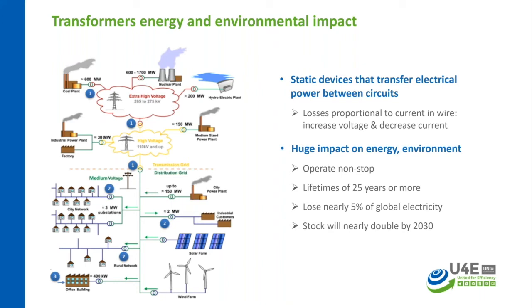In some cases, it will be even higher, and therefore this transformer becomes a very important product to regulate. Another important thing from the utility perspective is that this is a product where the technical losses are higher, and there is the potential to reduce those losses. These transformers, as you all know, work 24/7, and the life of this transformer is 25 years or even more. So having an energy efficient transformer is going to create a sustainable impact on the environment and also on the utility economics on a long-term basis.